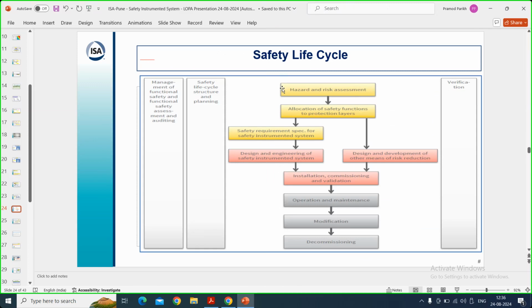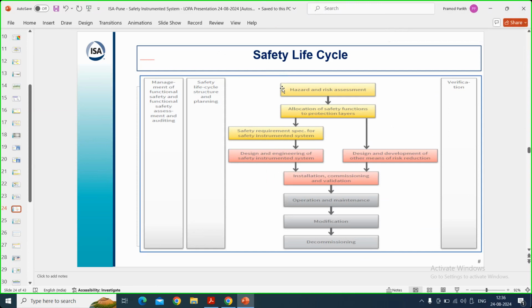SIL is a performance. Your SIL 3 performance will get declined to SIL 2 or SIL 1 or SIL 0 if you are not periodically testing, because your SIS is a dormant system. Your control valve, which has not operated for 5 years and was in open condition in normal plant running, when you want to operate it, it may not operate. So that means your SIL 3 rating has gone to SIL 0 rating.